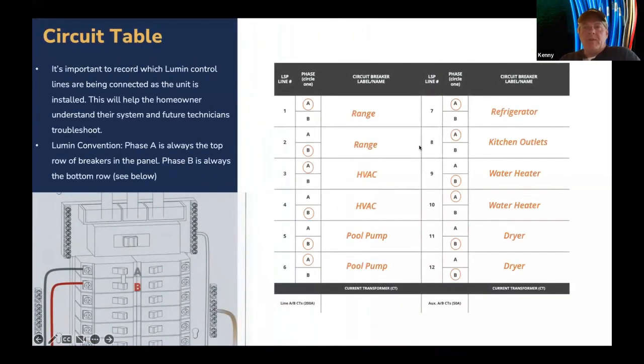That circuit table is also what we call, instead of referring to line 1 and line 2, since we have Lumin lines 1 through 12, we're just going to refer to each of the phases as breaker row phase A and breaker row phase B. And unless you have a crossover breaker, it's pretty much your odd and even number breakers, odd being A and even being your B row breakers.